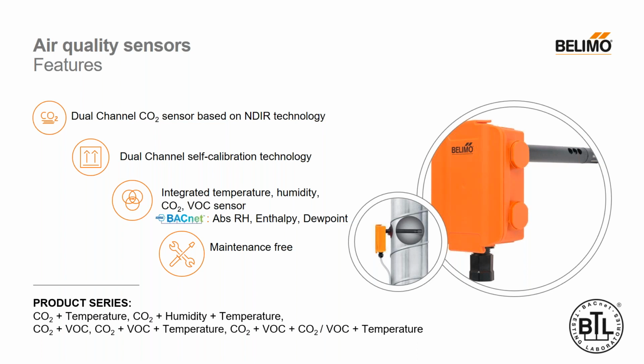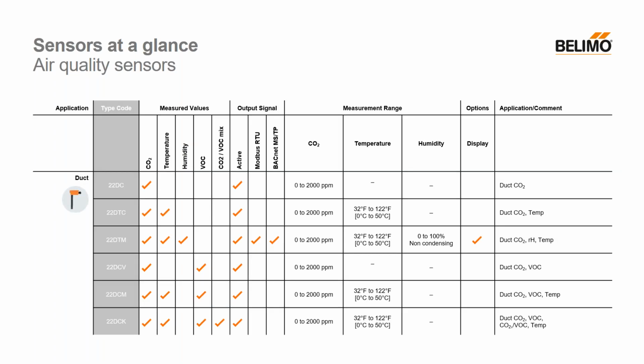We have CO2 by itself, CO2 and temperature, CO2 with temperature and humidity, CO2 and volatile organic compounds, as well as CO2 with VOC and temperature. So just a quick look at the overview of the air quality sensors. Again, keep in mind, anytime it's an active output, the part number is going to begin with a 22. That's going to indicate active. As you can see here, everything is going to have CO2 as a standard option. Then you can select from temperature, humidity, volatile organic compounds, CO2 or VOC mix. And we do have the BACnet and Modbus options available for the CO2 and indoor air quality sensors. They're also available with an LCD display, much like the temperature and humidity sensors that are available for duct mount applications.